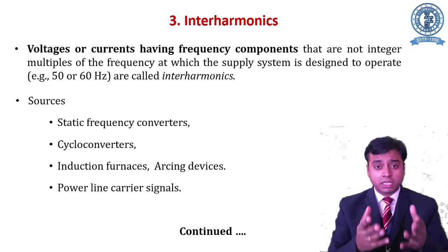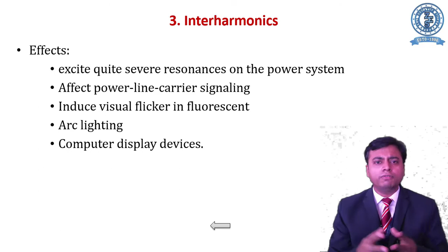Now, what are the effects of this? It is devastating. Why? It will create resonance in the system. It will create problems with the PLCC, that is power line carrier communication signals. It will cause flicker because of interharmonics. You will have flicker in fluorescent lights. The arc lighting will have some effects on it. Computer displays will not work properly. So these are some effects of interharmonics.